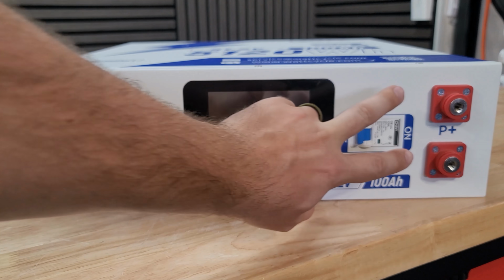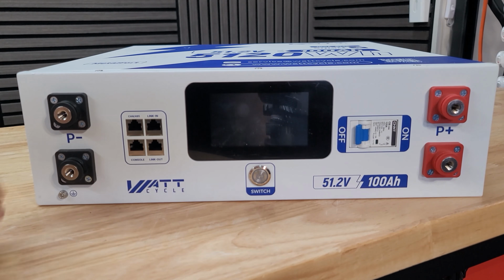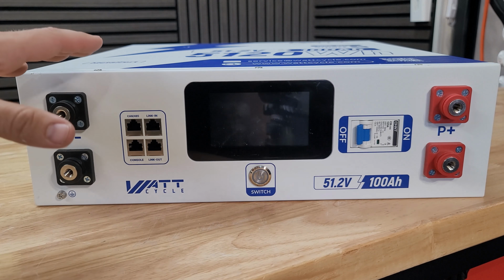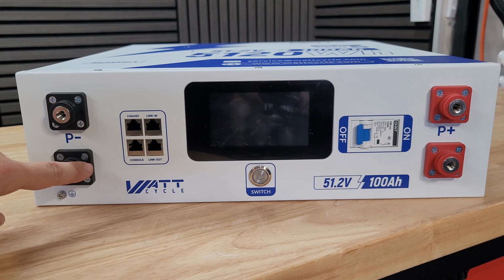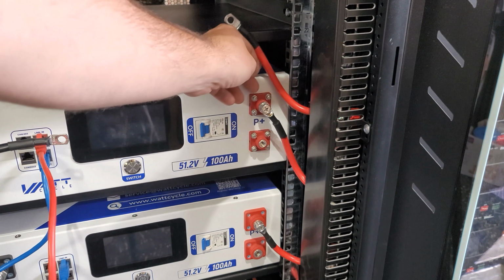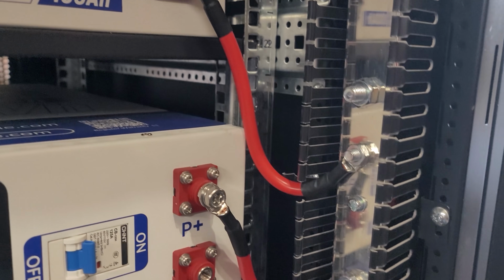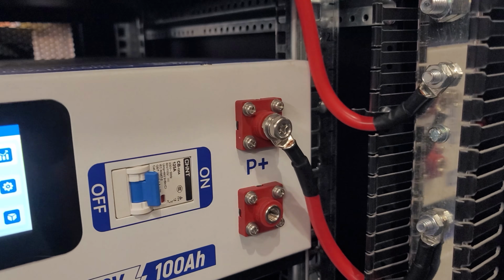Having 2 posts on each side makes life a lot easier, so if you're daisy chaining batteries vertically, you have all of these open spots. Or if you're using a server rack like this, you can just take the cable that comes with the battery and put that directly to the bus bar that is in the server rack itself.